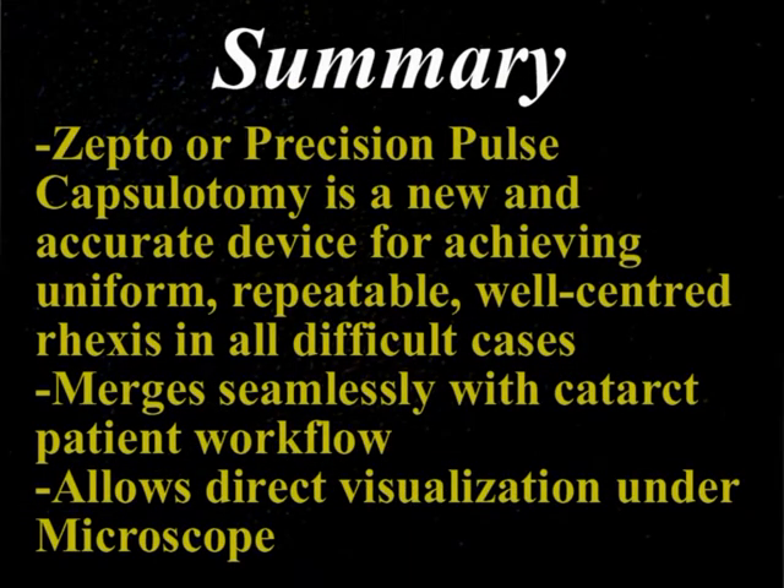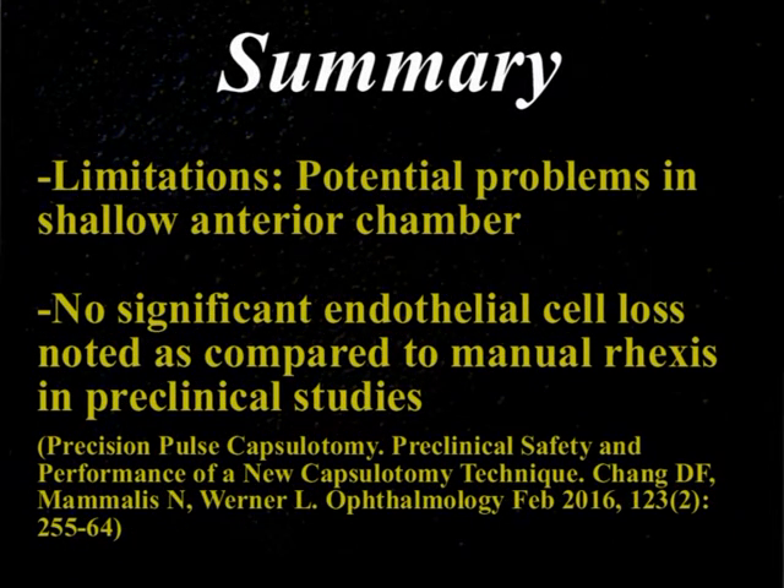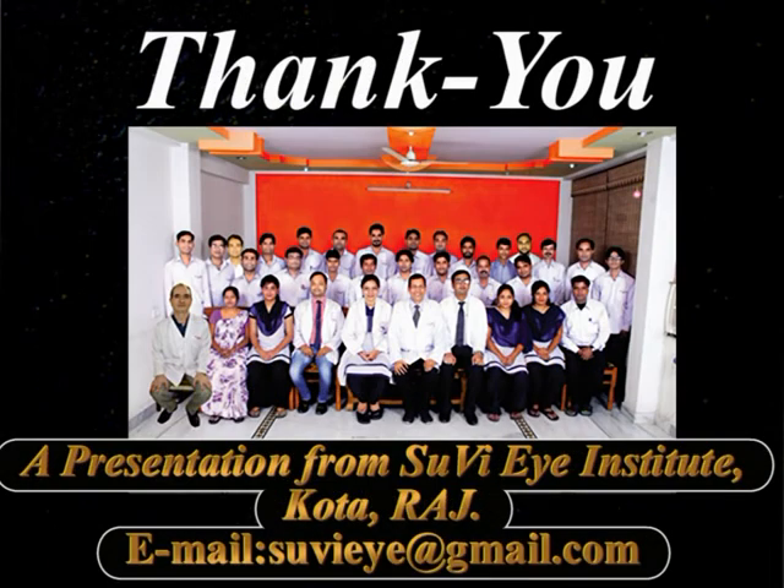In summary, the Zepto technique or precision pulse capsulotomy is a new and accurate device for achieving uniform, repeatable, well-centered capsulotomy in all difficult cases such as white cataracts, hyper-mature Morgagnian cataracts, and cases with anterior capsular fibrosis. It merges seamlessly with the cataract patient workflow, requires no additional rooms or space, and allows direct visualization under the microscope. A potential limitation is difficulty inserting the device in cases with a shallow anterior chamber. However, preclinical studies have shown no significant endothelial cell loss compared to manual rhexis in contralateral eyes. This technology can achieve a good capsulotomy in difficult cases and expand the use of premium IOLs.